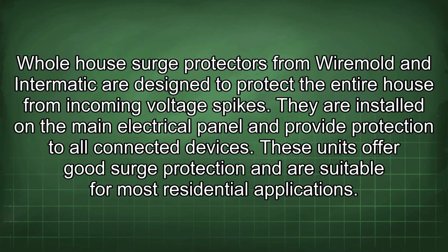Whole house surge protectors from WireMold and Intermatic are designed to protect the entire house from incoming voltage spikes. They are installed on the main electrical panel and provide protection to all connected devices. These units offer good surge protection and are suitable for most residential applications.